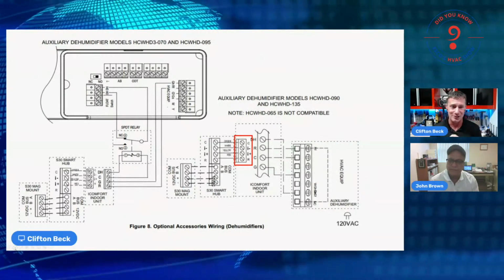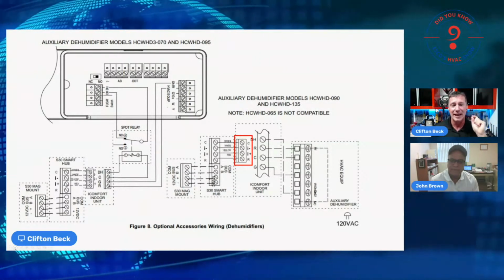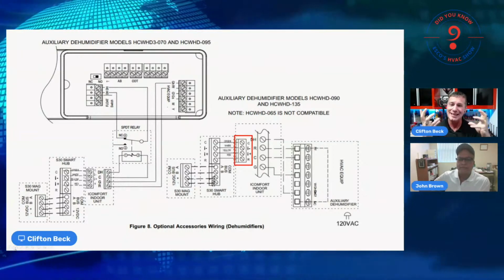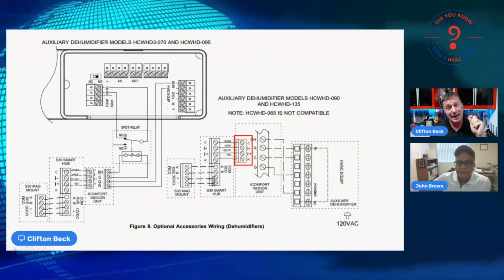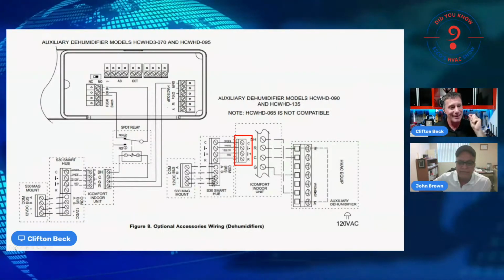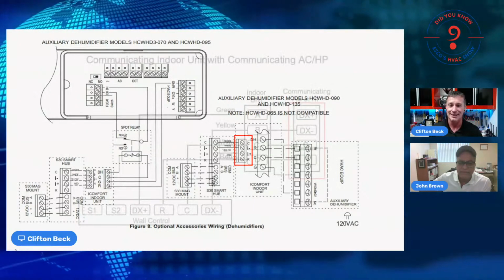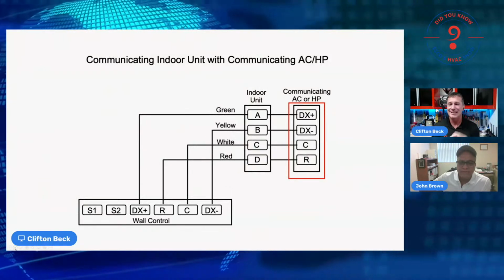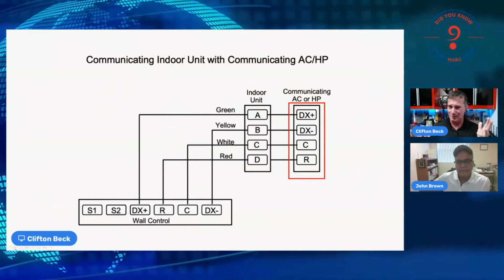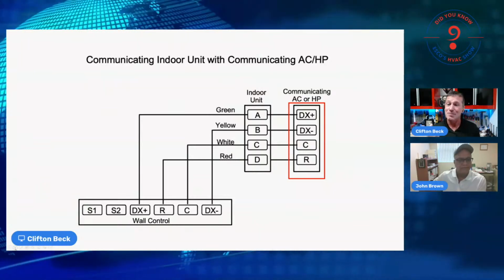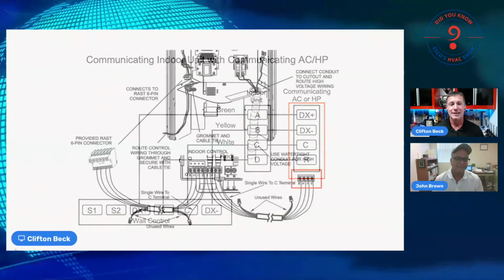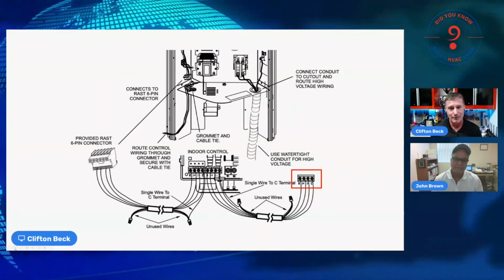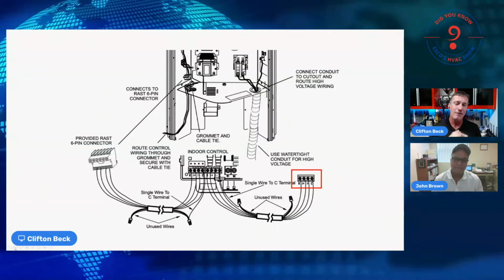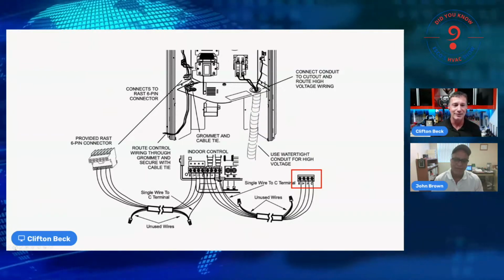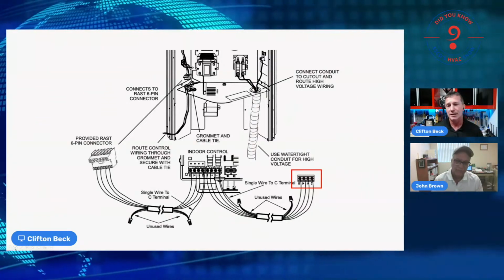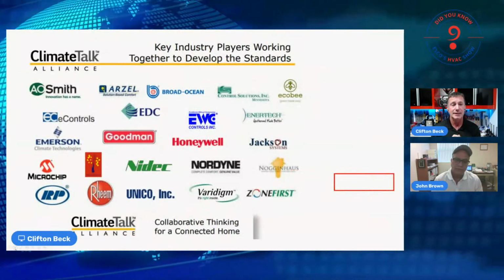Looking at this other manufacturer, in that little red square we see our common and our R, our 24 volt AC load, and here they label it as I negative and I positive — again a negative reference and a positive reference. This one shows a 4-wire connection: two for 24 volts AC, and two labeled as positive DC and negative DC. So we see another reference of the exact same thing. I'm not saying all manufacturers use the exact same approach — I've seen some variations — but the philosophy, the technology behind it all, comes from a similar design.